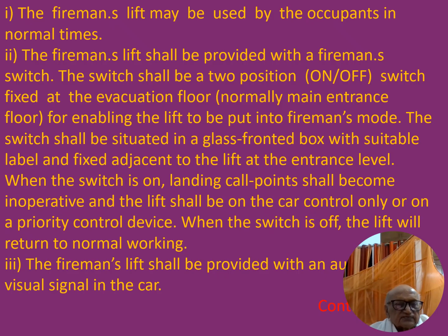Friends, the fireman's lift may be used by the occupants in normal times. The fireman's lift shall be provided with a fireman's switch. The switch shall be a two-position on or off switch fixed at the evacuation floor level, normally the main entrance floor, for enabling the lift to be put into fireman's mode. The switch shall be situated in a glass-fronted box with suitable label and fixed adjacent to the lift at the entrance level. When the switch is on, landing call points shall become inoperative on all the floors, and the lift shall be on car control only or on a priority control device. When the switch is off, the lift will return to normal working.